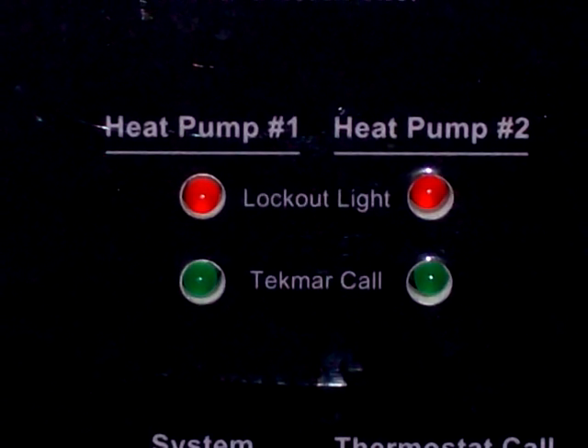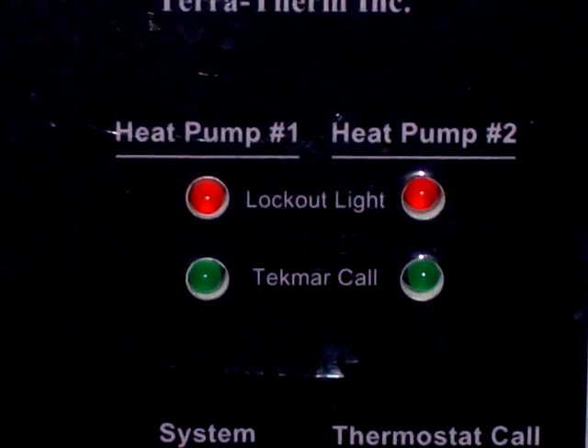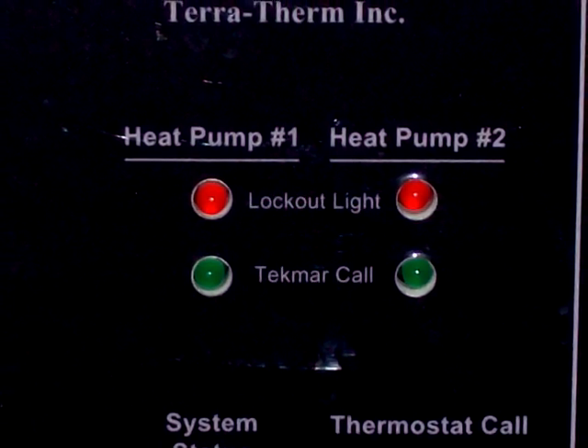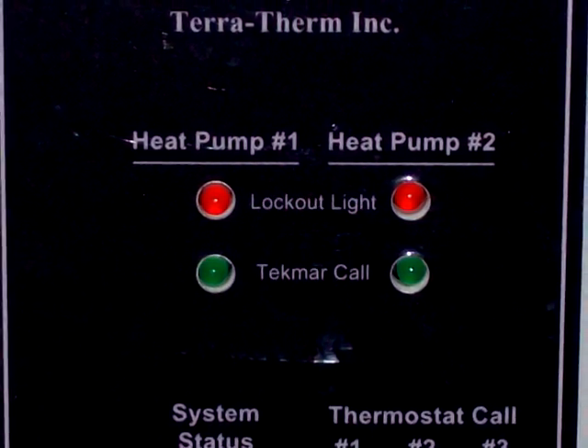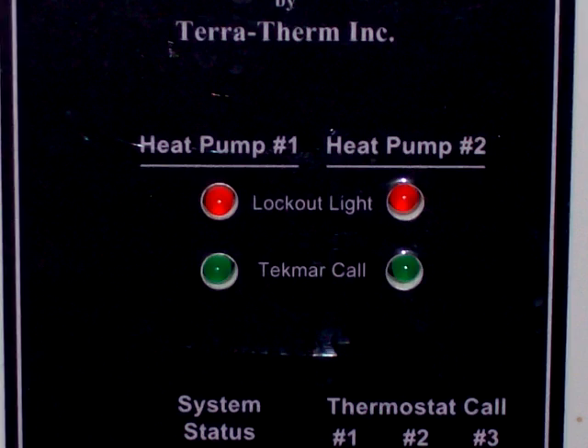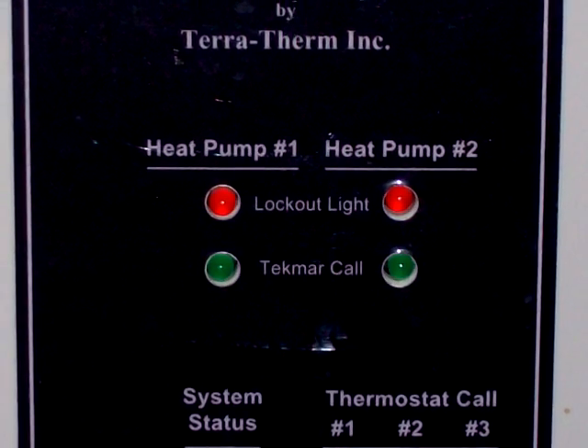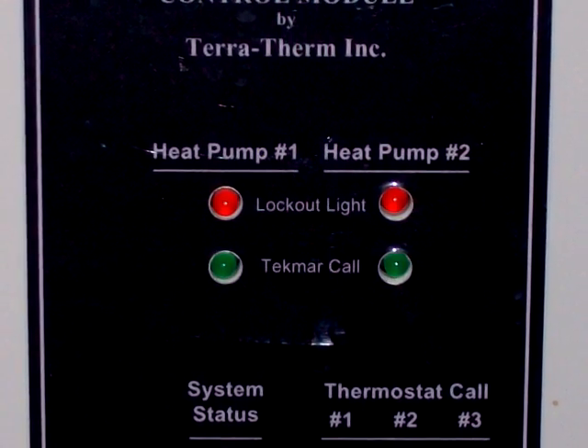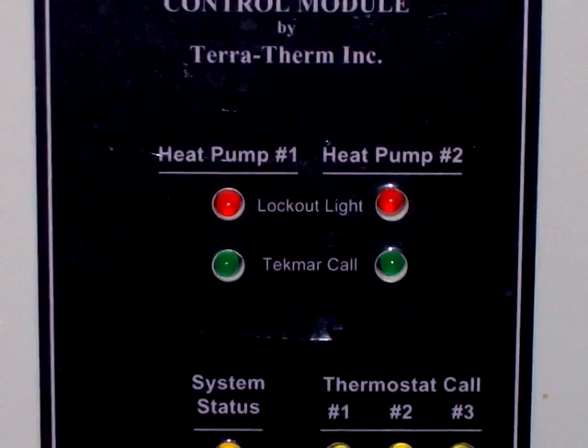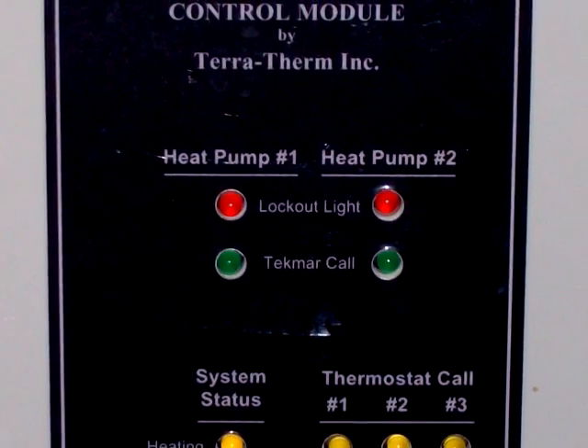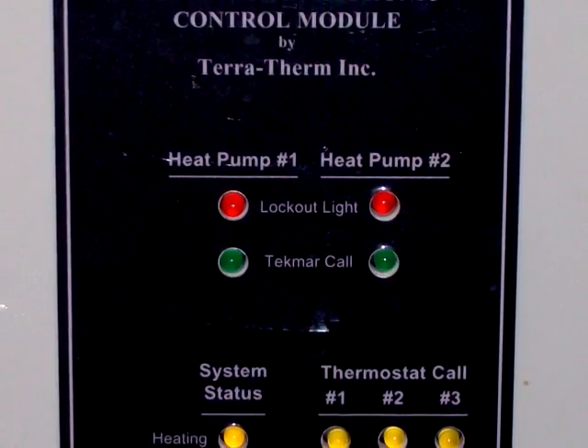The 4 upper lights are the heat pump status lights. The green light indicates a call from the buffer tank for either heat pump 1 or 2, if you have a dual compressor or dual heat pump system. The red lights indicate a heat pump lockout situation for either heat pump 1 or 2.